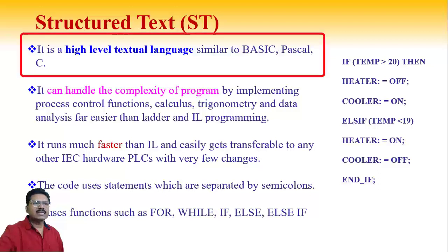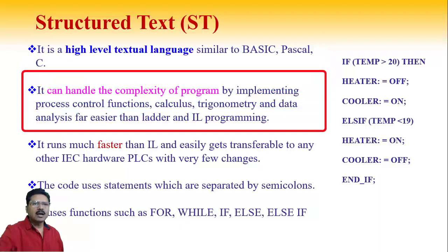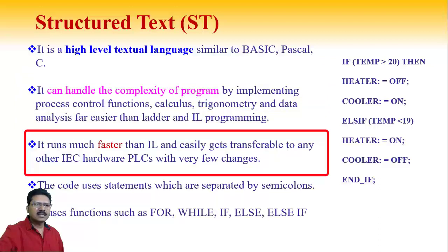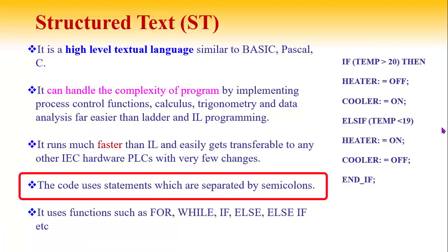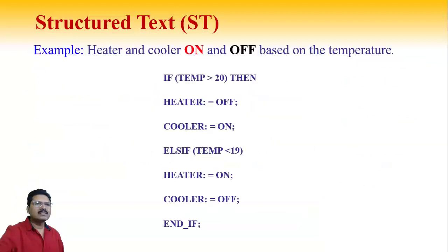Next is Structured Text. It is a high-level textual language similar to BASIC, Pascal, C, C++, etc. It can handle program complexity by implementing process control functions, calculus, trigonometry, and data analysis — far easier than Ladder and Instruction List. It runs much faster than Instruction List and is easily transferable to other PLC hardware with very few changes. The code uses statements separated by semicolons, and it uses functions such as FOR, WHILE, IF, ELSE, ELSE IF, etc.